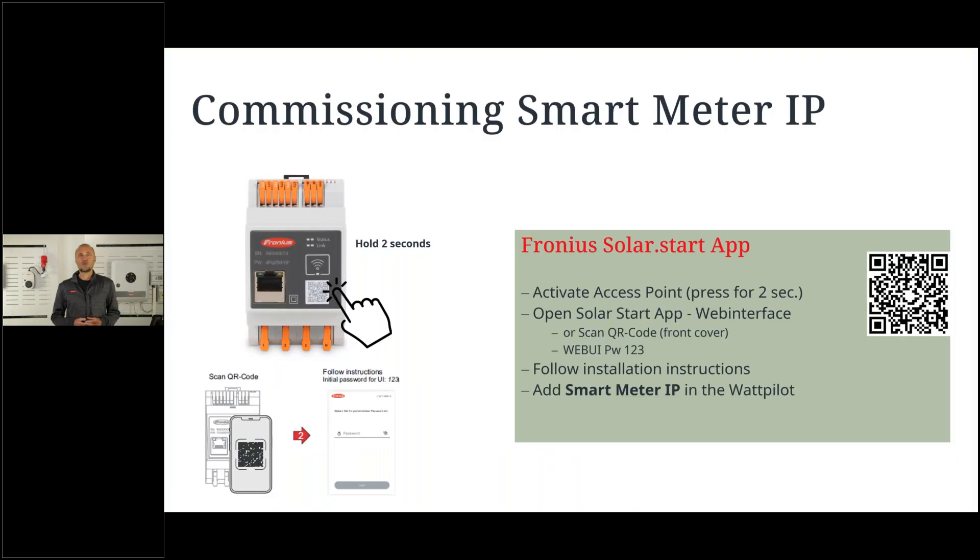For commissioning the Smart Meter IP: press the button for two seconds after starting the system. The access point opens; connect your smart device — using the Solar.start app for example — scan the QR code, enter the password '1234', then follow the instructions for the CT settings and Smart Meter settings. Once connected, you will receive an IP address. Note this down, as it will be used in the Wattpilot to confirm the correct Smart Meter IP is paired.